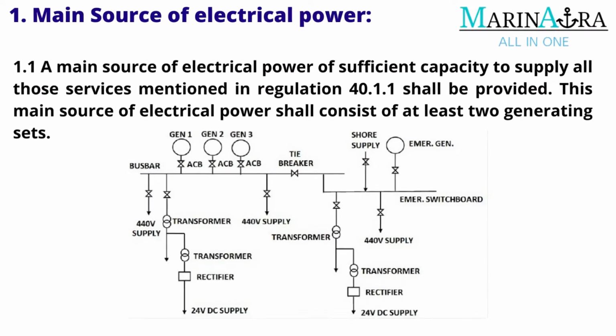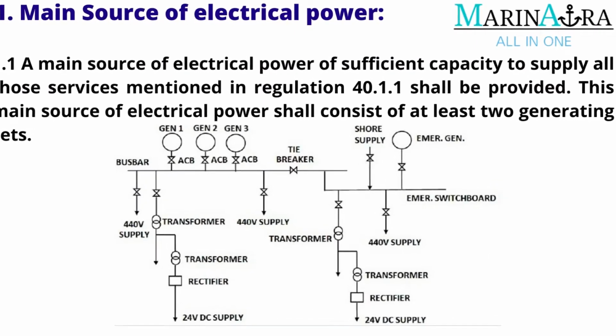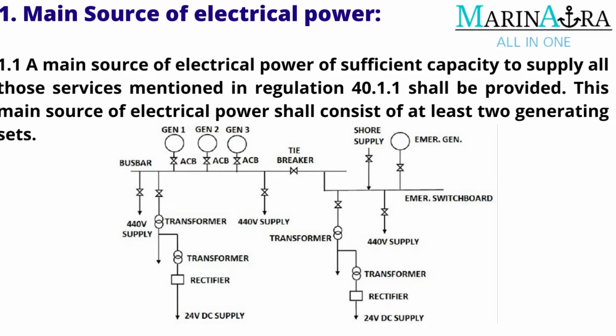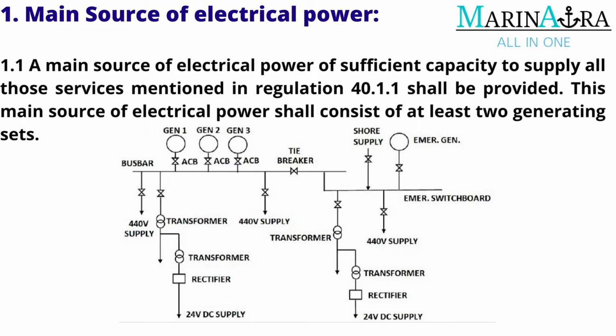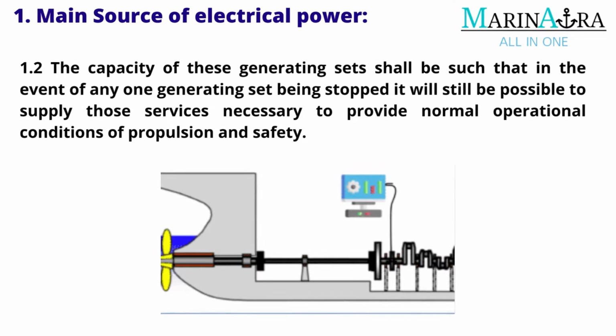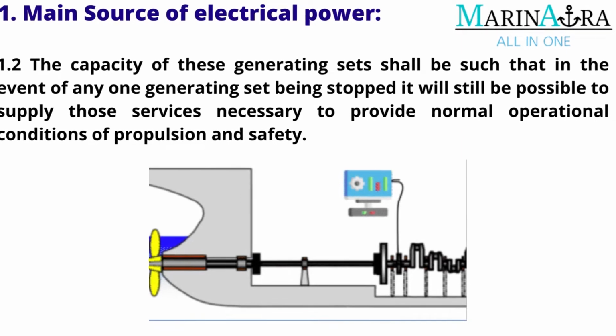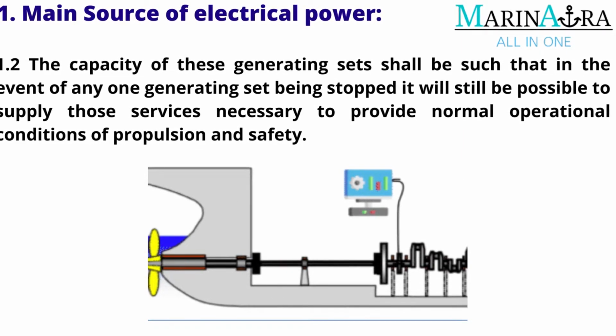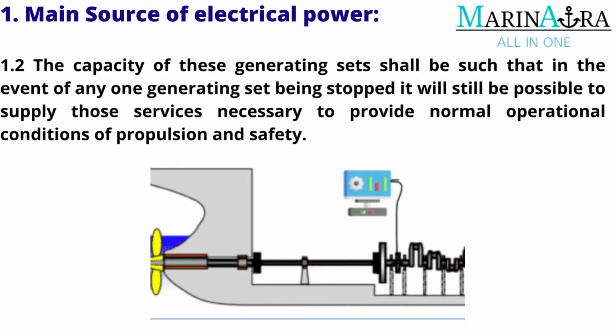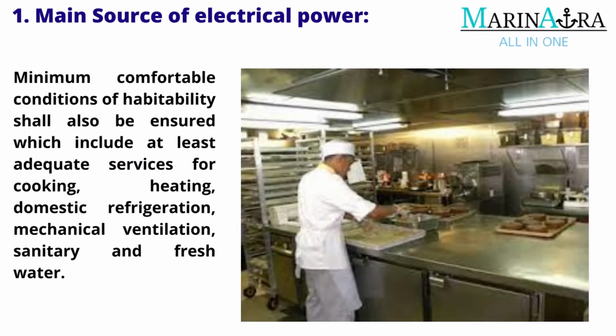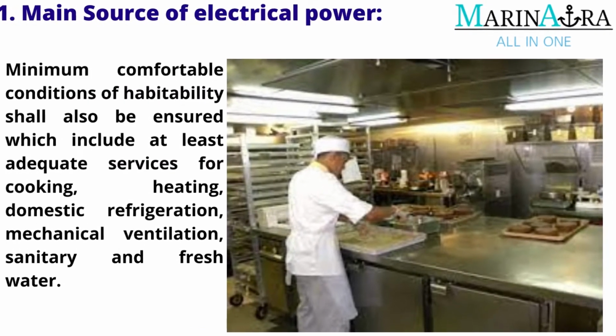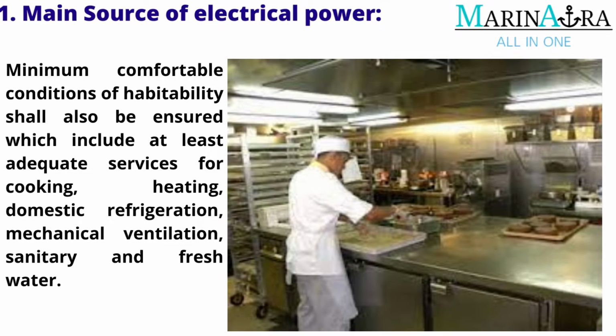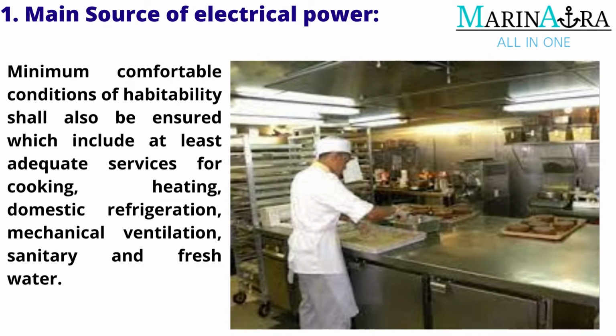A main source of electrical power of sufficient capacity to supply all those services mentioned in Regulation 40.1.1 shall be provided. This main source of electrical power shall consist of at least 2 generating sets. The capacity of these generating sets shall be such that in the event of any one generating set being stopped, it will still be possible to supply those services necessary to provide normal operational conditions of propulsion and safety. Minimum comfortable conditions of habitability shall also be ensured, which include at least adequate services for cooking, heating, domestic refrigeration, mechanical ventilation, sanitary and fresh water.